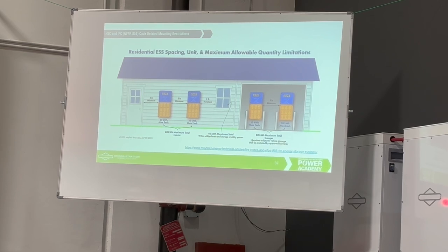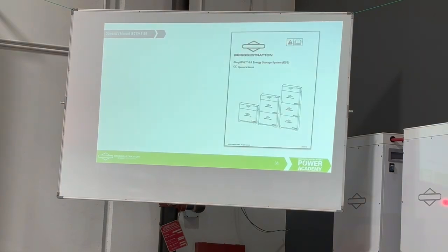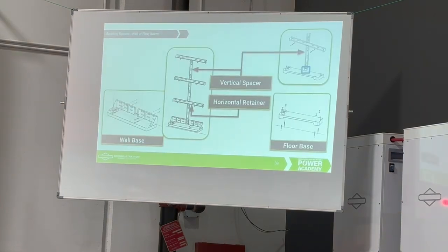And if LA requires 36 inches, that's the requirement for us anyway, right? According to code, for now, yeah. But in Orange County, I do the same installation compared with LA, and I can go 6 inches spacing between batteries, based on the manufacturer's specification and documentation. If I go to LA with the same setup, yeah, it has to be 36.